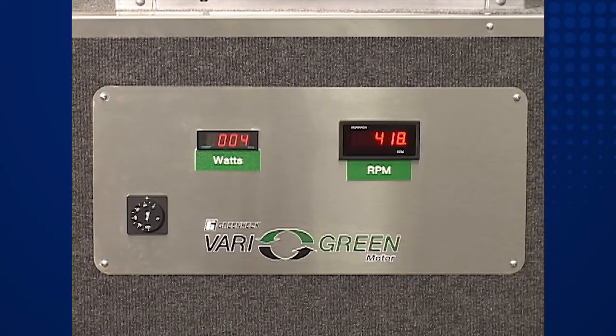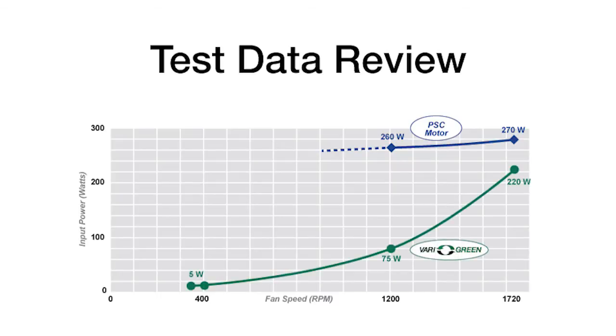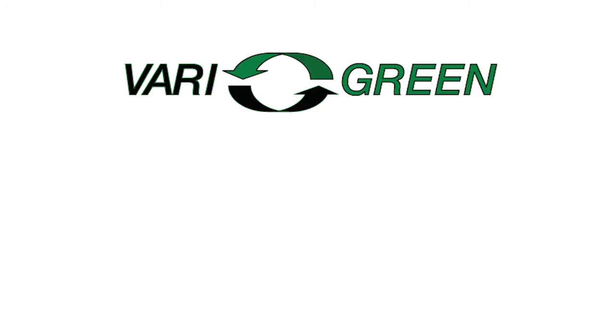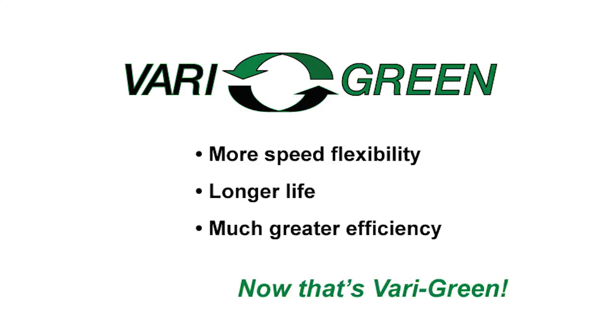As a summary, let's review our test data in a graphical format. As we observed, the PSC motor draws nearly the same power regardless of fan speed and has a recommended fan speed turn down of just 30 percent. The far superior VariGreen motor is more efficient at high speed and offers dramatic energy savings as fan speed is reduced. Savings range from 20 percent to more than 70 percent depending on fan speed. Plus, VariGreen offers stable and cool operation down to 350 RPM — more speed flexibility, longer life, and much greater efficiency. Now that's Vari-Green.